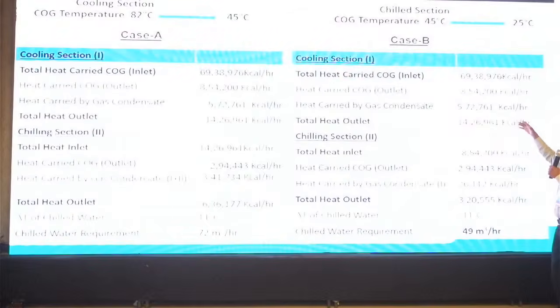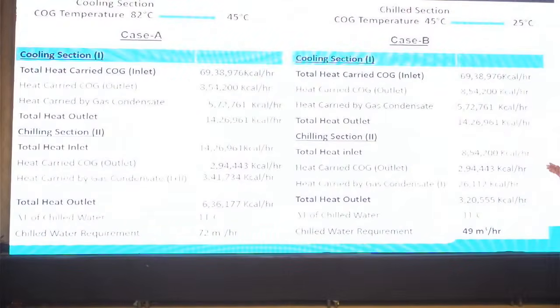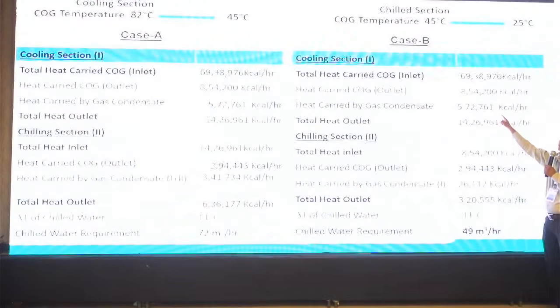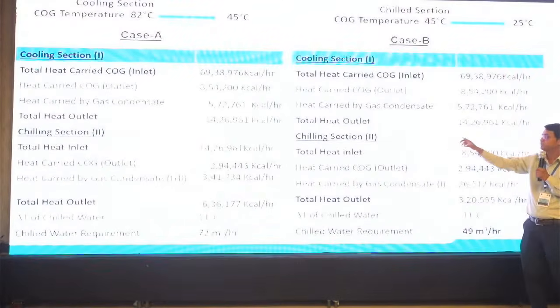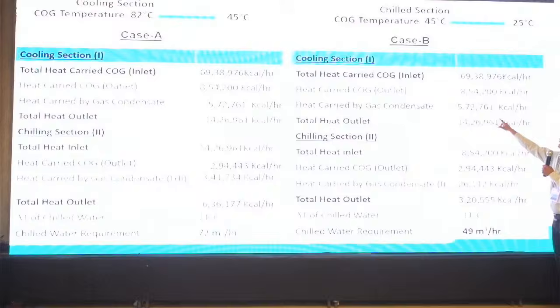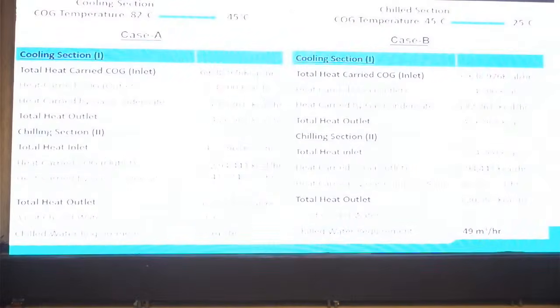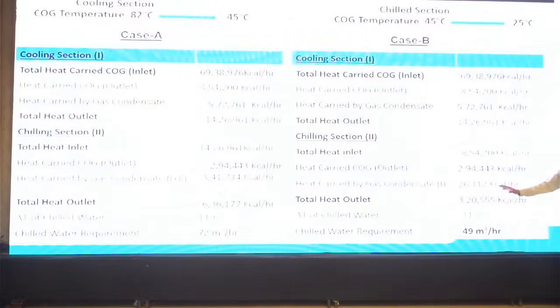But if you go to case B, what I told - the heat from whatever condensate accumulates in the upper section of the cooling part - goes to the seal pot. So this heat will not go to the chilled water section. Earlier, this total heat was going to the chilled water section, but in case B, we are taking this amount of heat out.